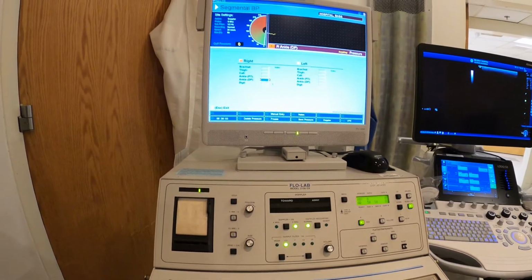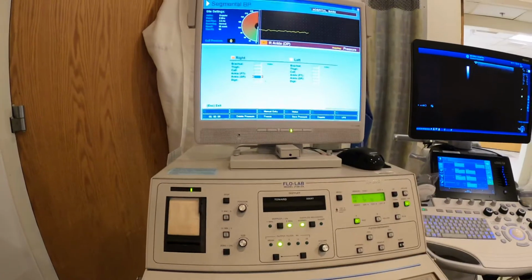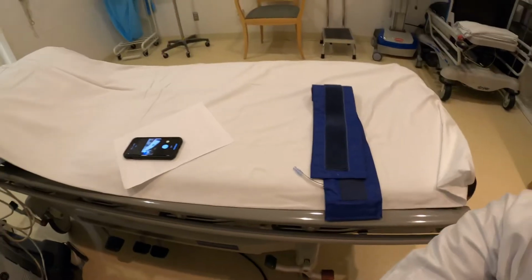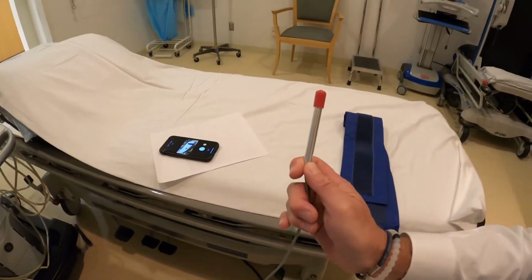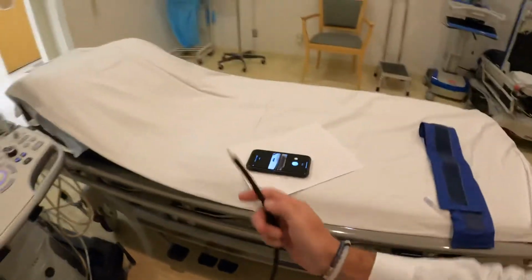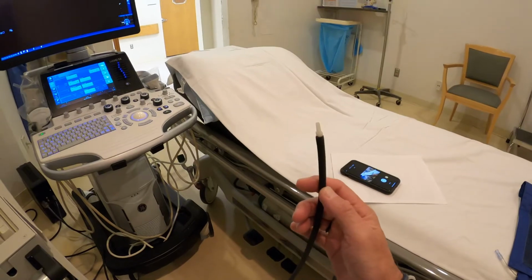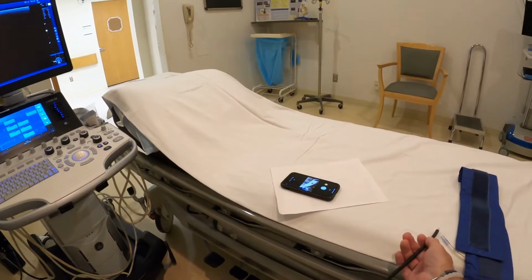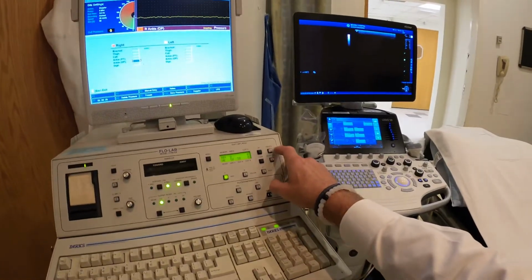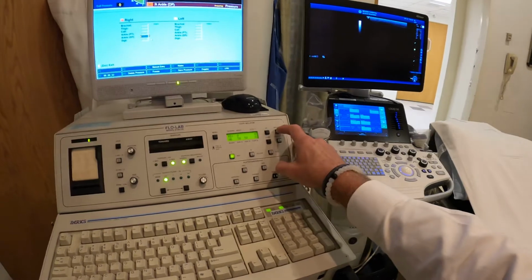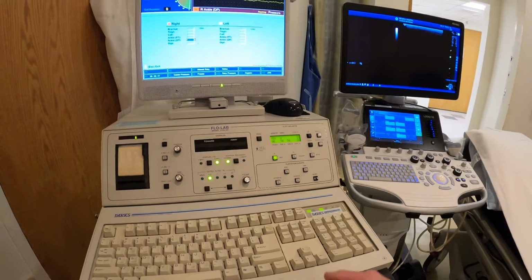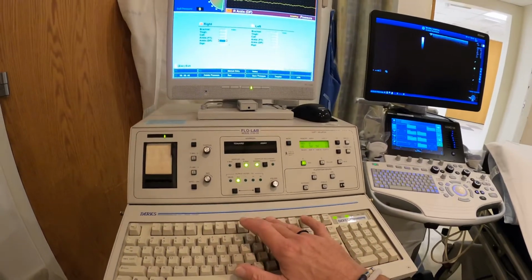Then it automatically goes to the segmental pressure of the right DP or AT. I would use my dark blue cuff, Doppler, take the red thing off obviously, and you want to use the hose with the nipple on it. So, obtain your signal. What you would do is inflate the cuff by hitting inflate right here. It automatically inflates to a pressure. Once you get to that pressure, you take it off. It'll slowly deflate. When you hear that signal return, hit F9.